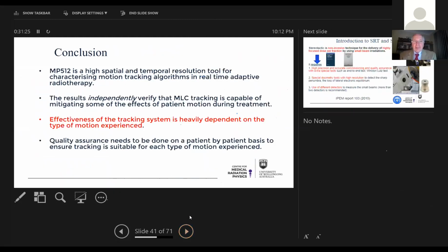So for this part, I would like to conclude that MP512 is a high spatial and temporal resolution tool for characterizing motion tracking algorithms in real-time adaptive radiation therapy. The result independently verifies that MLC tracking is capable of mitigating some of the effect of patient motion during treatment. So we're getting about 85% improvement. Effectiveness of the tracking system is heavily dependent on the type of motion experienced. This is exactly what I mentioned to you, that for some patients it's not so big a benefit, not 85%, it can be 60%, 70% improvement.